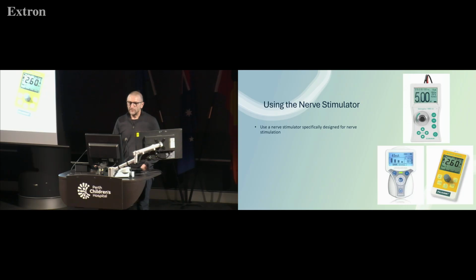But using nerve stimulators, you want a nerve stimulator that's specifically designed for nerve stimulation. It should be a constant current generator. What that means is the resistance, or more accurately, impedance of the tissues and the nerve, the needle, can be quite variable between different patients, and a constant current generator nerve stimulator will maintain a constant current despite variations in those.